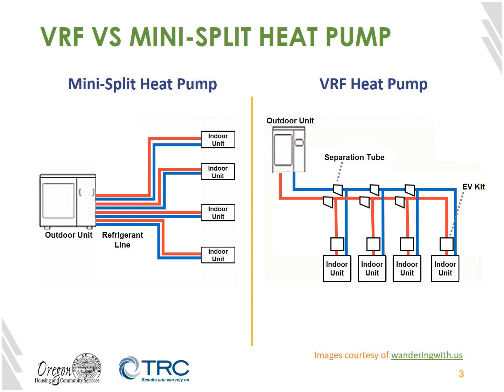So let's visually look at the difference between mini-split or multi-split heat pumps and a VRF heat pump. On the left side of the screen, you'll see the mini-split heat pump system. In this scenario, you have a set of refrigerant lines, sometimes referred to as the hot gas and suction line, or the high pressure gas and low pressure gas lines. And you have a set that runs independently from the outdoor unit to each indoor unit or head. Now, there are some configurations and scenarios where you may have a single set of lines coming off of the outdoor unit going into a distribution box, which will then deliver to each individual interior unit. That is sometimes determined by the specifics of the equipment and can also be mandated by codes and regulations in order to limit how many different places you may have connections.